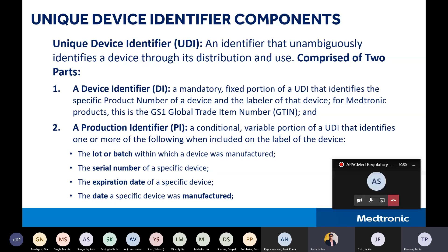Okay, so what a UDI is not: it is not a unique number representing a single individual device. This is not serialization. When a product is serialized, that's when a UDI represents a single device. An important concept is that the catalog number or reference number may have many device identifiers associated. You should not assume that it's going to be a one-to-one relationship where a catalog number or reference number only has one device identifier. I know this has been a challenge in hospitals where they have their systems set up to be one-to-one, and I will be speaking about this on the next slide. There are going to be cases where there are multiple device identifiers that still represent the same catalog or reference number.